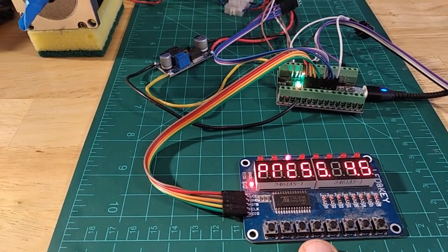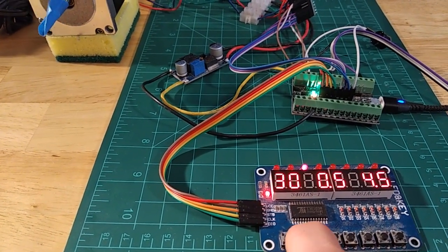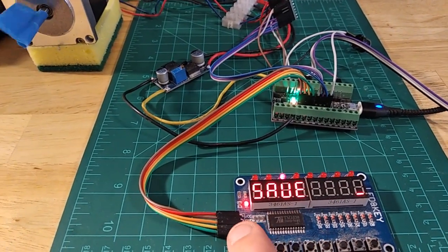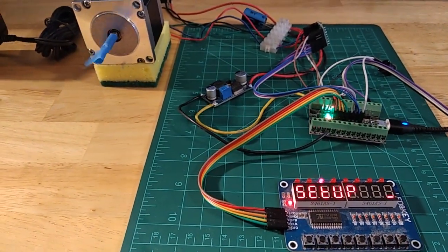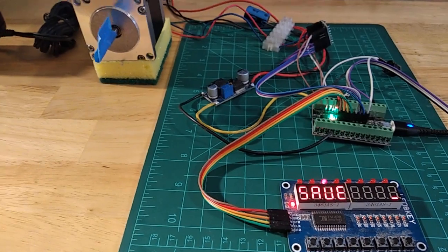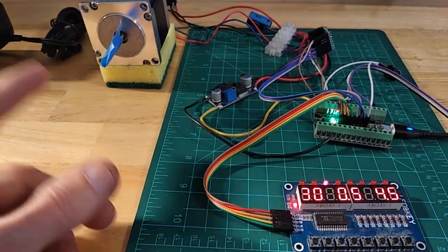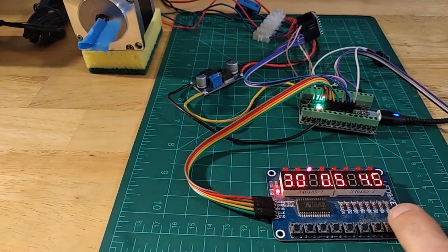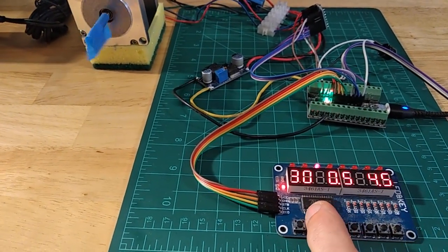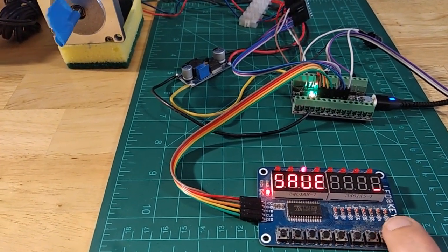So here it is now. And once you have set all the parameters, you can save the setup so that when you restart the machine, it will use these values from the start. One interesting point is it allows you to have the machine that starts and immediately starts ventilating. So it depends if it's running or not at the time where you save the data. Let's save it now. Save setup, yes.